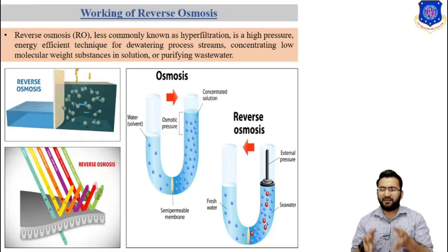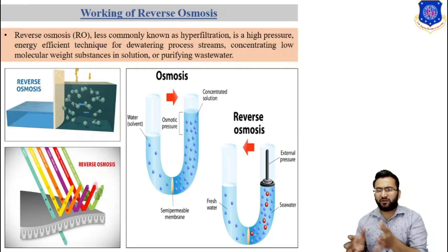Reverse osmosis is a liquid-driven membrane separation process, with the membrane capable of passing water while rejecting microsolutes such as salt or low molecular weight organics. Pressure as a driving force is needed to overcome the force of osmosis that causes water to flow from the dilute permeate to the concentrated feed.